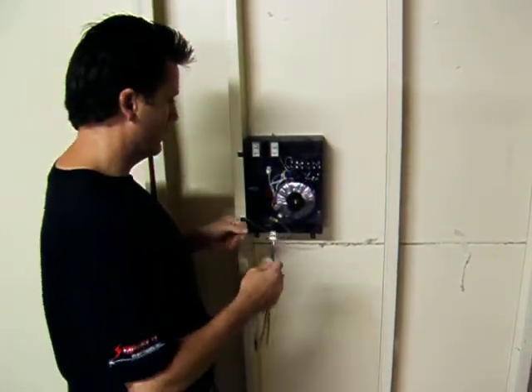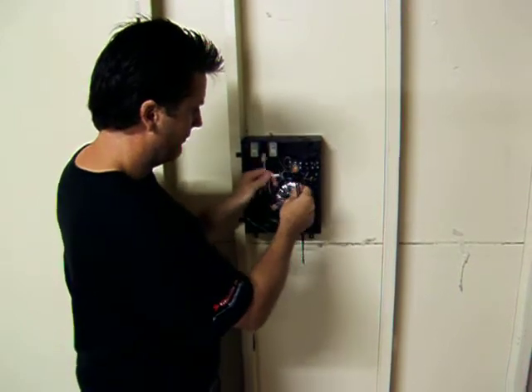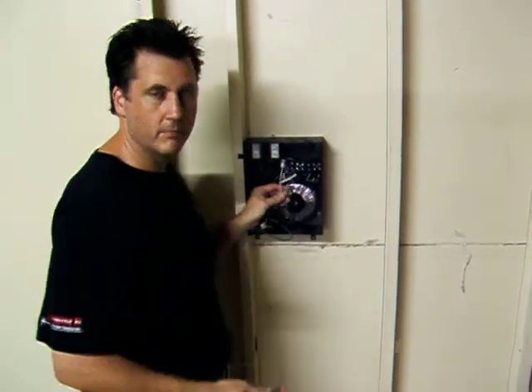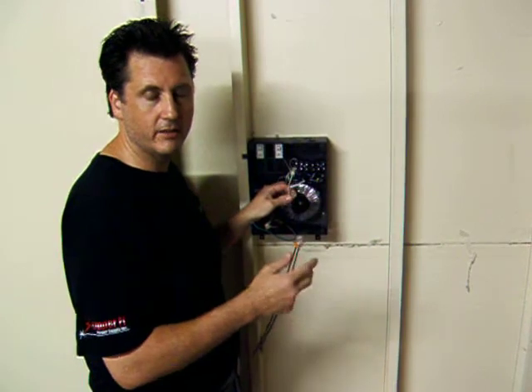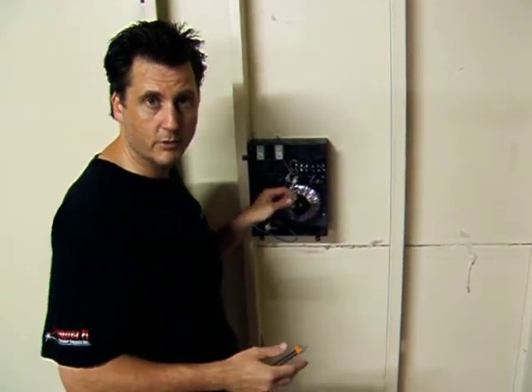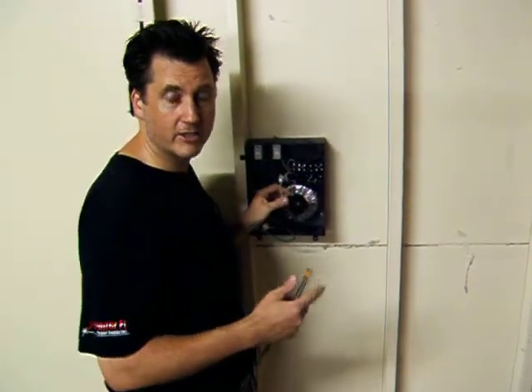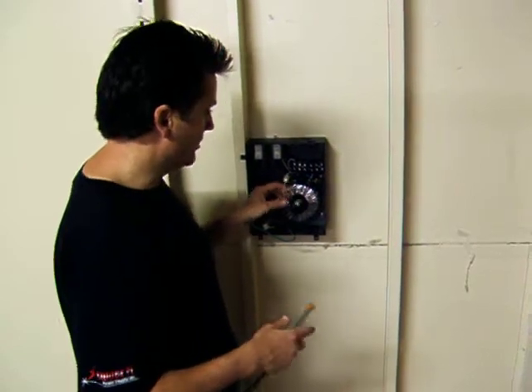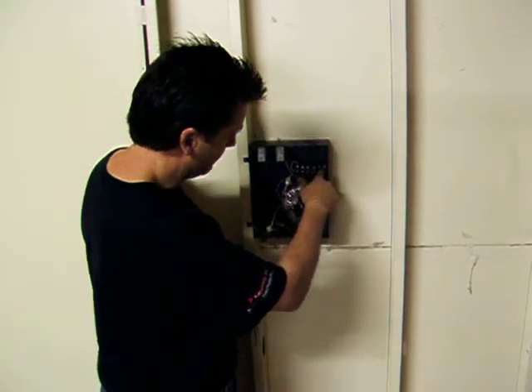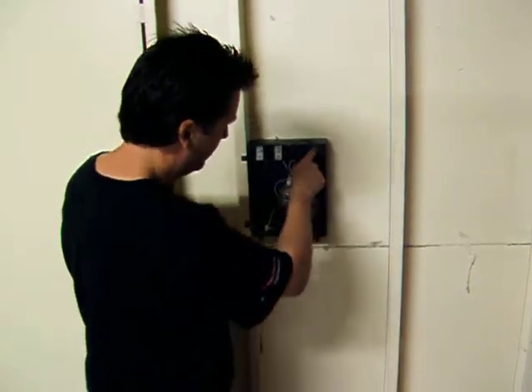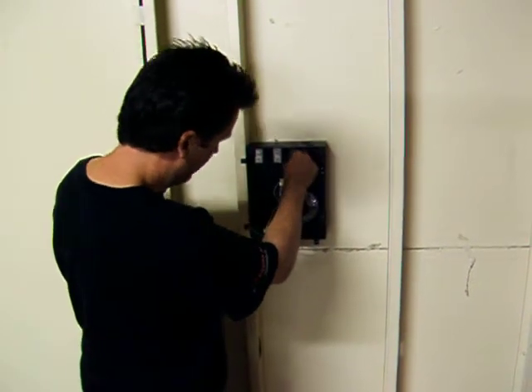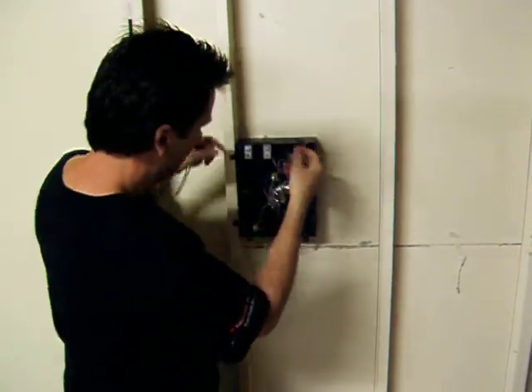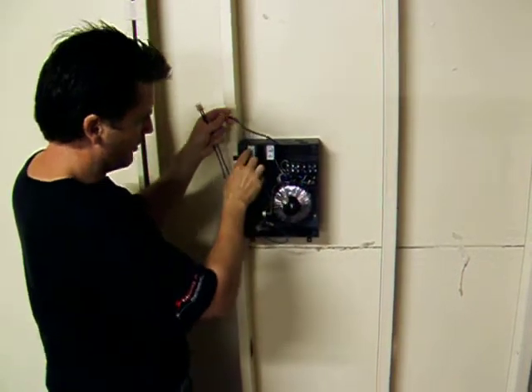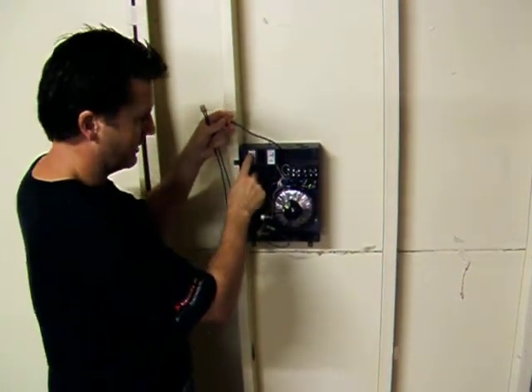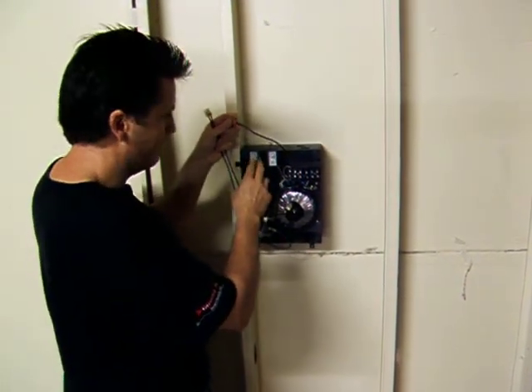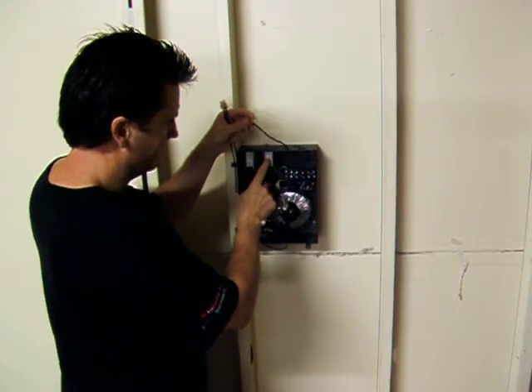So if you decide to choose these two and you measure your voltage in the field and you need to boost the voltage, well, on our standard transformers we have the boost taps on the secondary side. Now, how do you wire the taps on the secondary? In this case you've got a primary breaker here labeled primary. That controls the input. This is your secondary breaker.